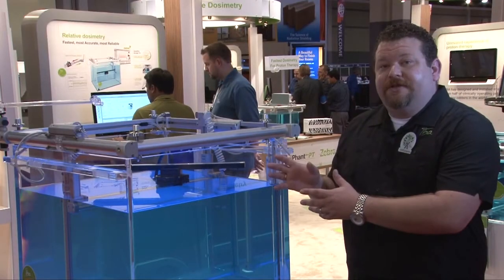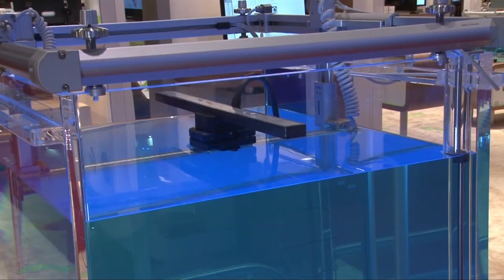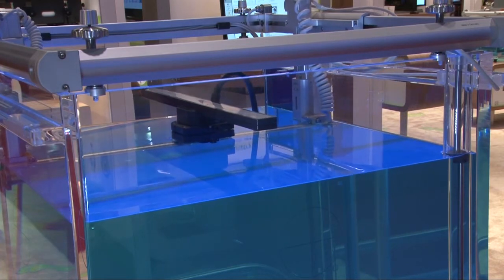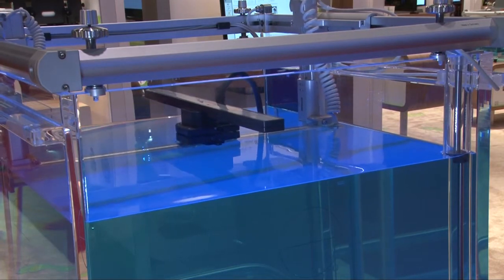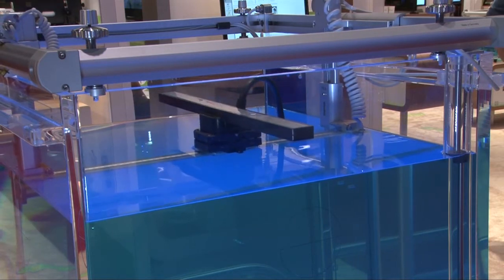One of the key features of the speed of commissioning with IBA Dosimetry Commissioning Services is the use of the Linear Diode Array. The Linear Diode Array allows us to commission a machine five times faster than with a single thimble ion chamber or a diode.